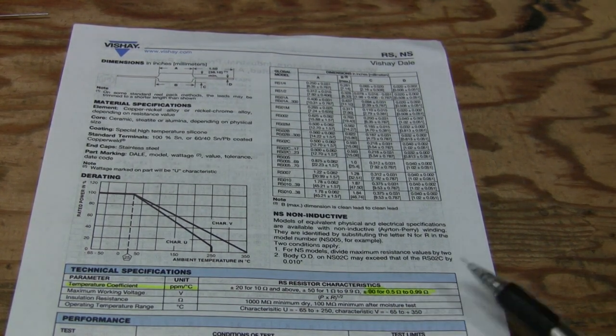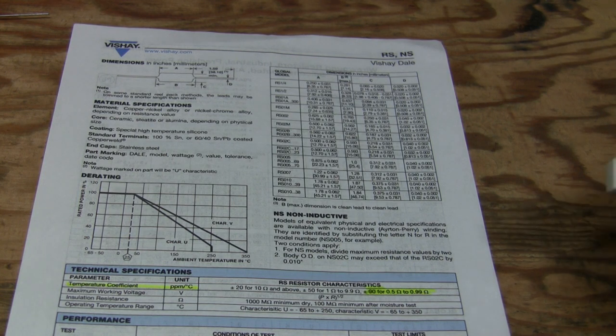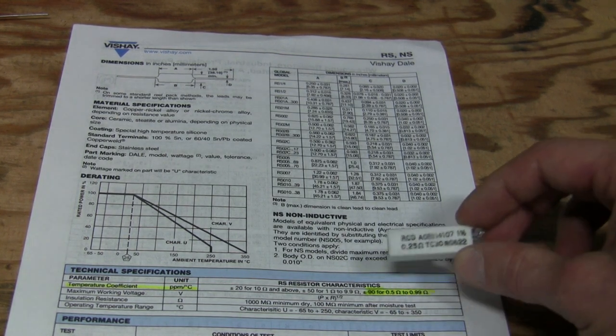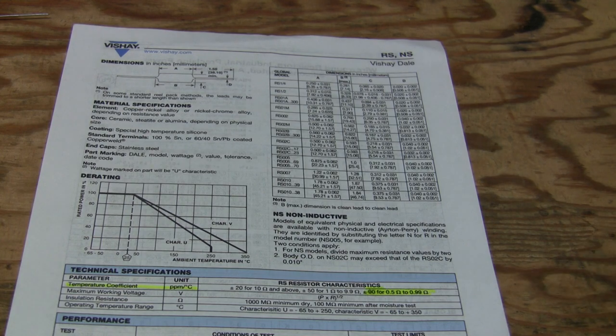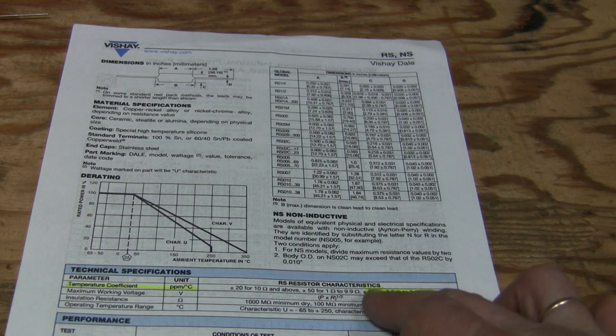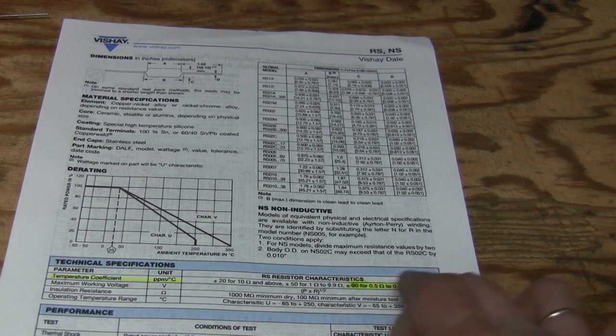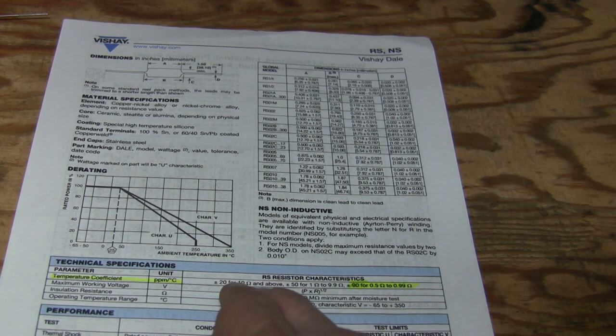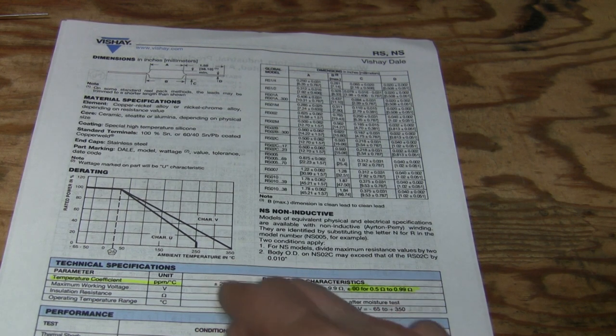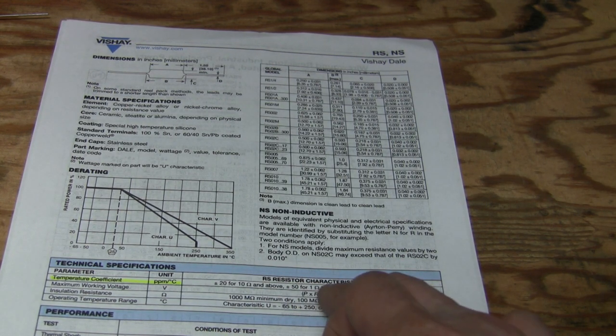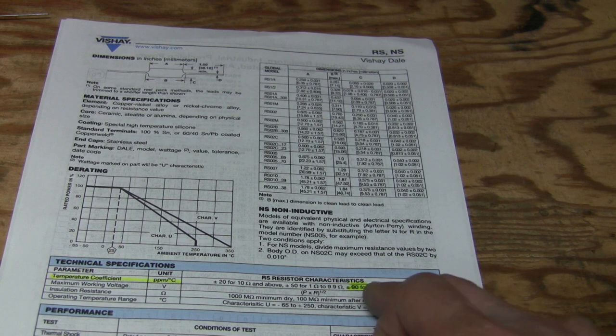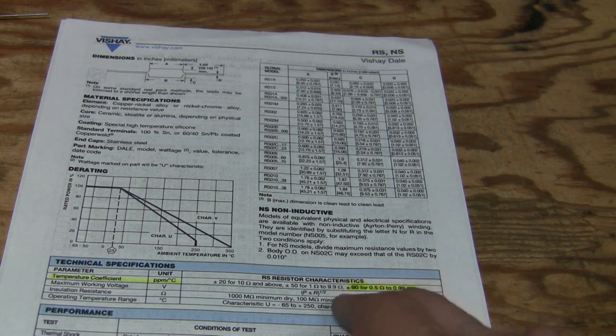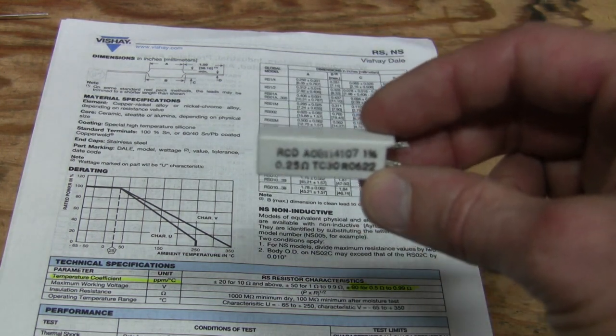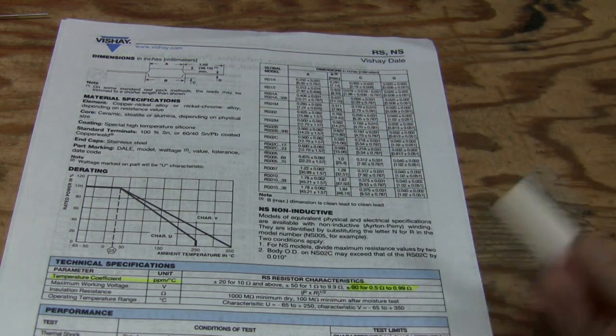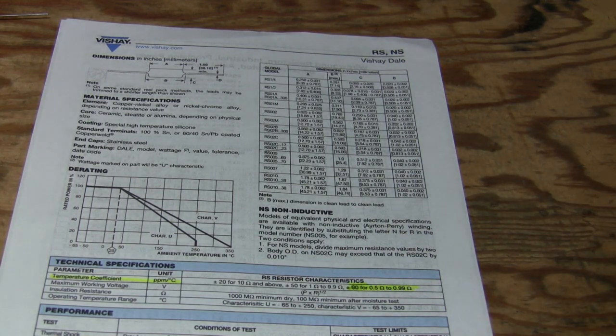So all I can see is that they're comparable in this sense, in the temperature coefficient. Let's assume it's slightly higher because it goes higher and higher. For 10 ohm range and above, they have 20 ppm. From 1 ohm to 10 ohm, 50 ppm. And for this low range, 1/2 ohm to 1 ohm, 90 ppm. This one was rated at 150. Not sure exactly, but looks like they're similar in this sense.